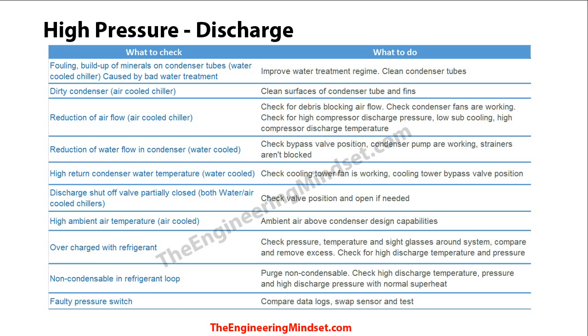On the flip side, with air-cooled chillers you're going to have dirty condensers. Over time, especially after rain, dirt can block the air-cooled chiller condenser fins and tubes. Make sure all tubes and fins are cleaned regularly, but remember the tubes contain refrigerant and are very delicate — use light brushes and fin combs.